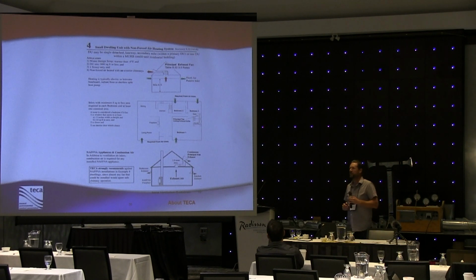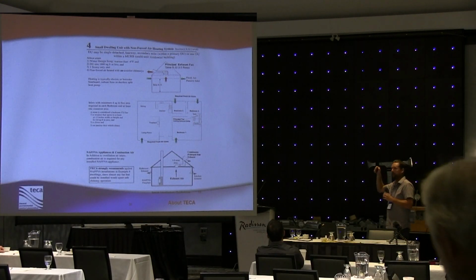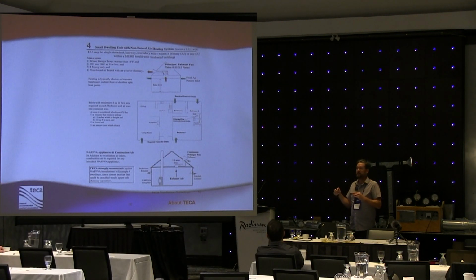And the main reason is because if it's noisy, people will try to shut it off, right? The other thing is I like to see contractors that are installing those principal exhaust fans try to pick a bathroom. I know we do in our outfit. We try to pick a bathroom that is typically not the master ensuite, because the ensuite or the master bedroom is usually occupied the most, and quite often those bathrooms are large bathrooms as well.